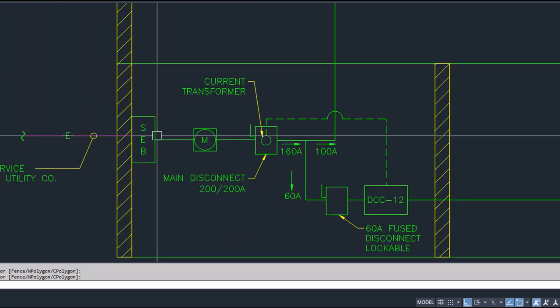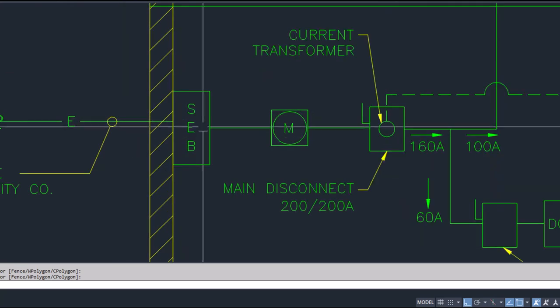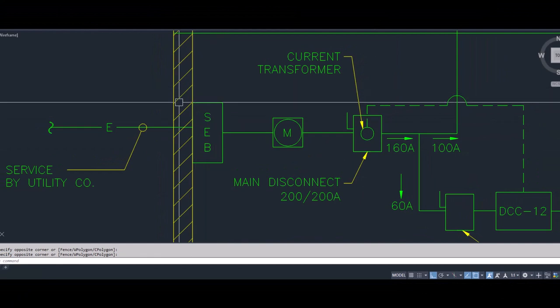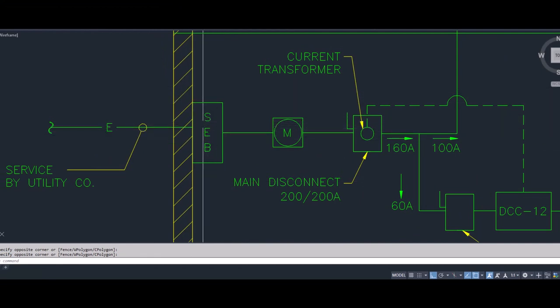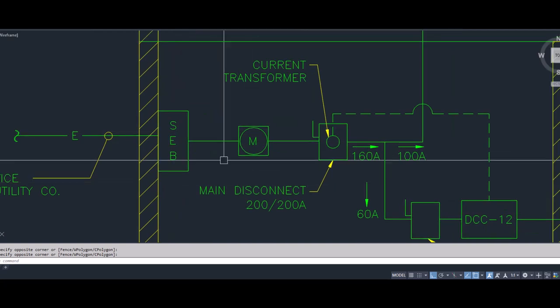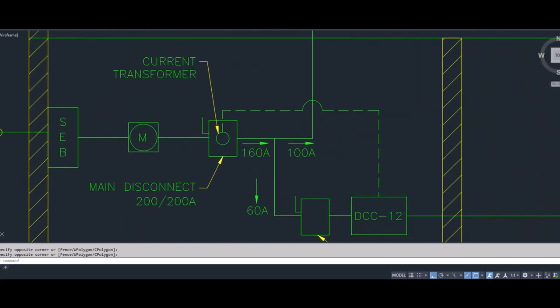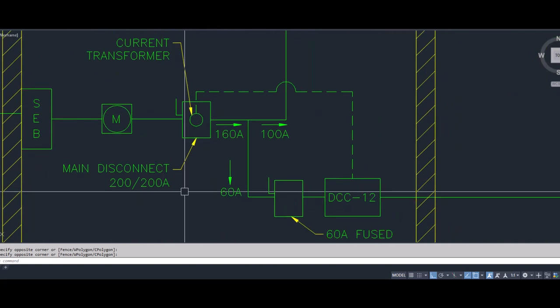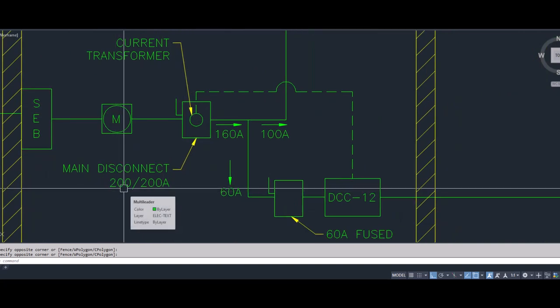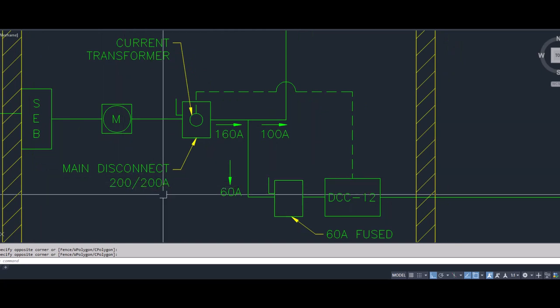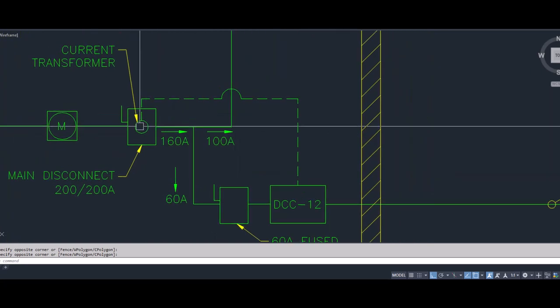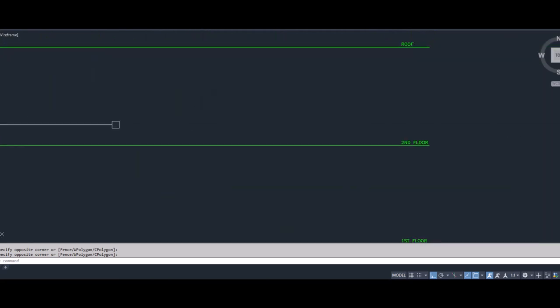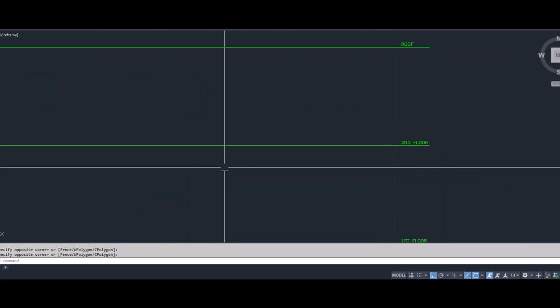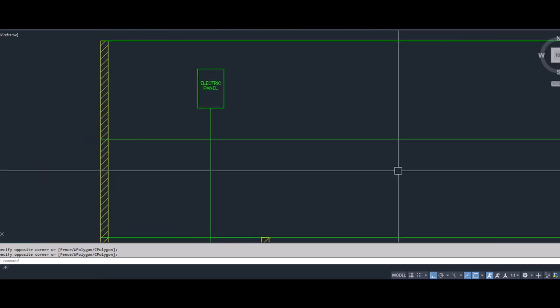It comes into the building, into a box called the service end box. And this is where the utility company will make connections to the wiring that's the property of the tenant. Then it goes into their meter, and it goes into their disconnect. In this example, it's a 200 amp rated fuse disconnect. All right, and the fuse is at 200 amps. And it goes in and it goes up to the tenant's panel, which in this example is the second floor, but it could be on the 30th floor or any other floor.